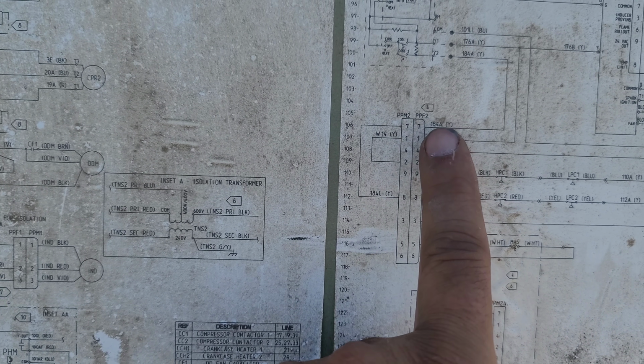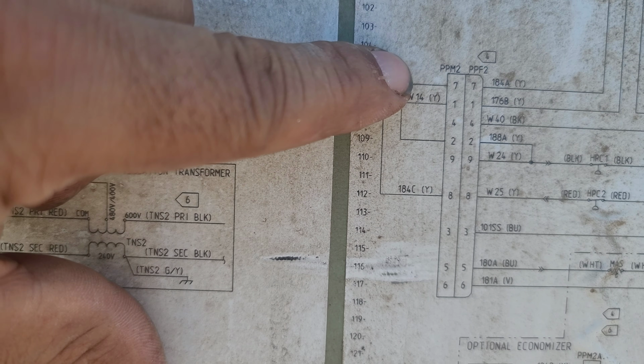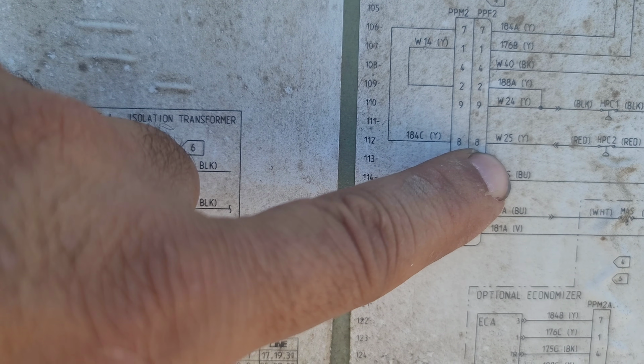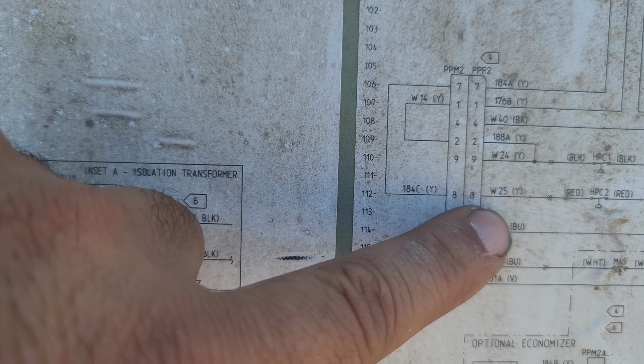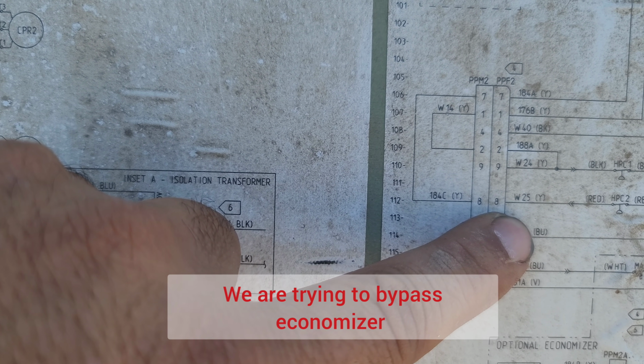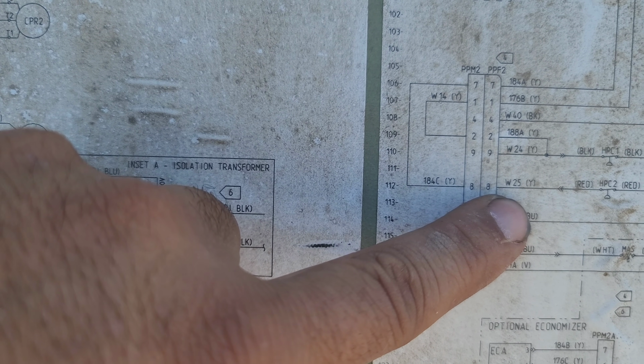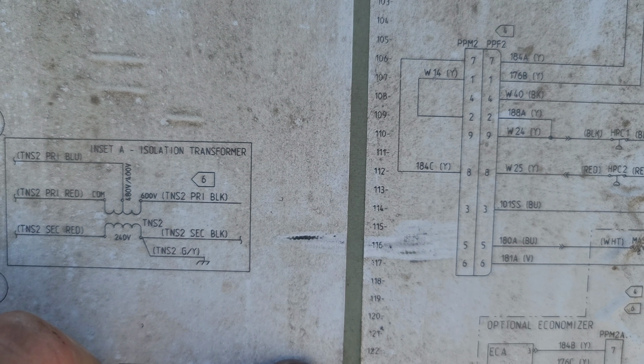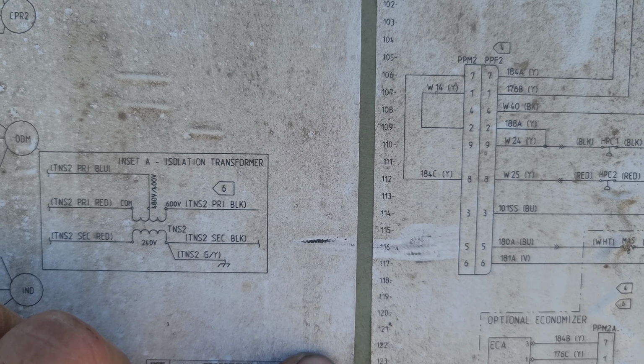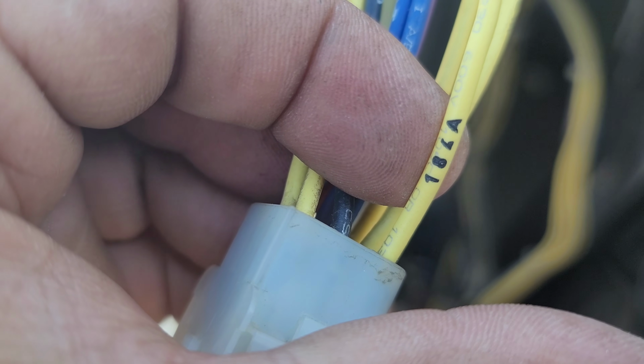So this is our economizer board here, and to bypass we have to connect as per this arrangement. So number 184 is our Y1, so 184 is going to number 8, so we have to connect between 184A and W24 to bypass, sorry, W25 here, 184 W25 to connect Y1. So this is W25, and the second one is, sorry, not this one, this one. This says here 184, so we have to short these two wires.